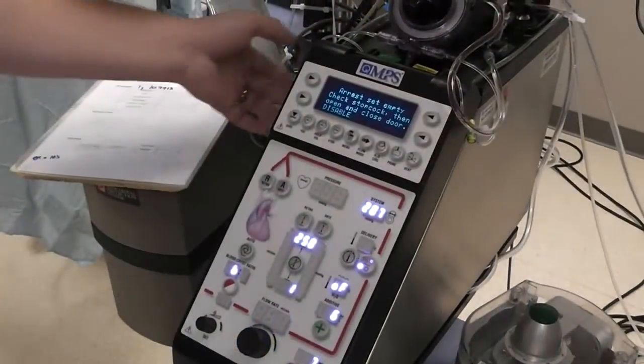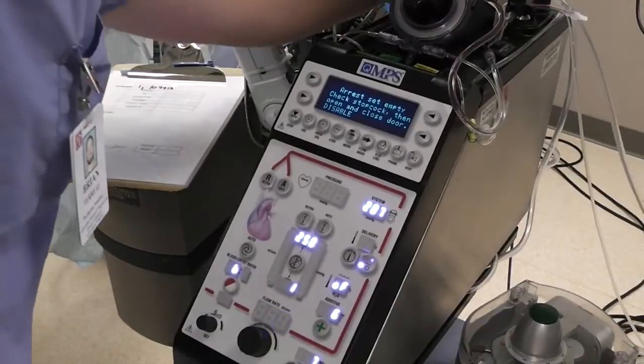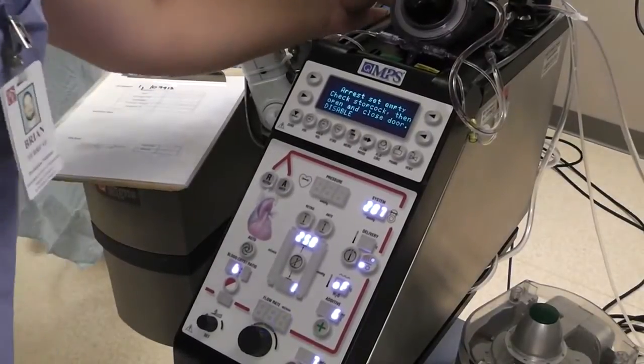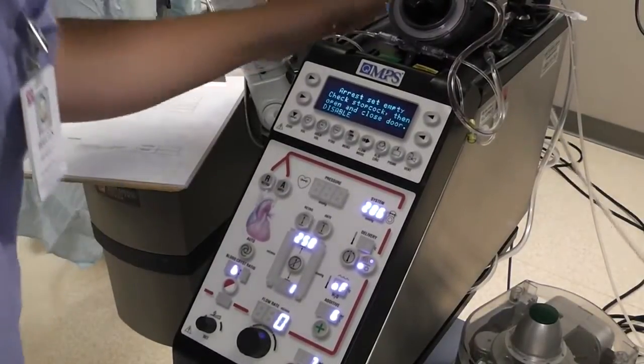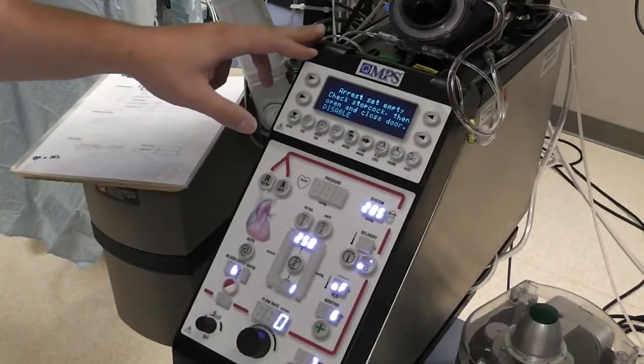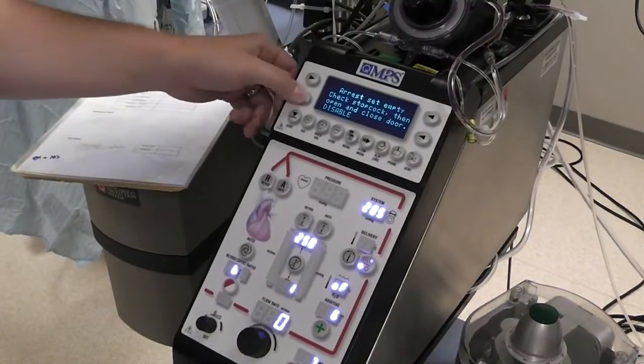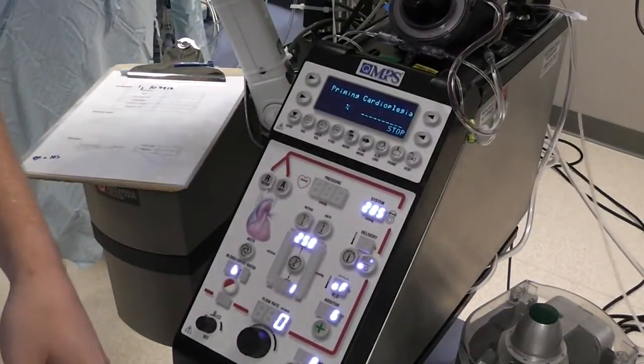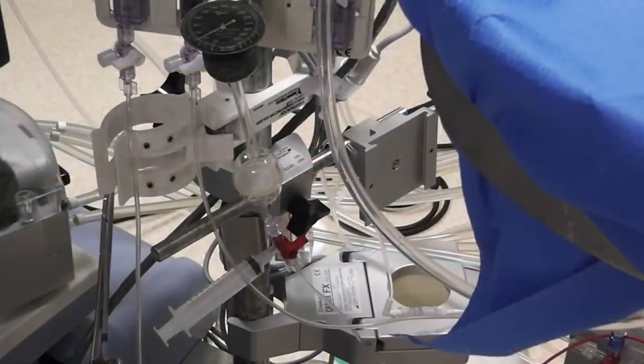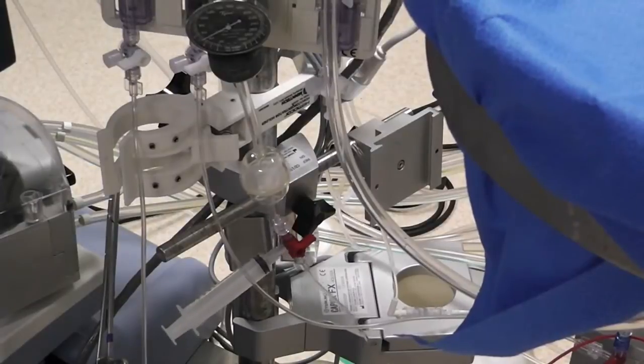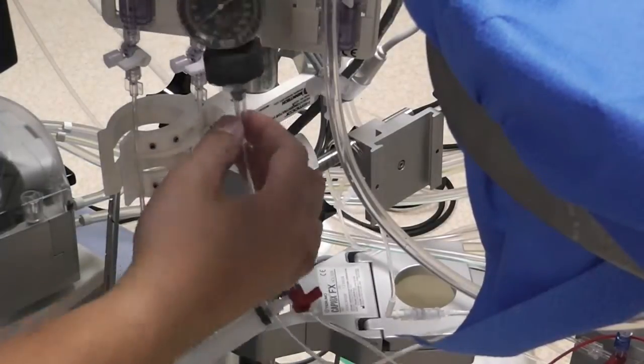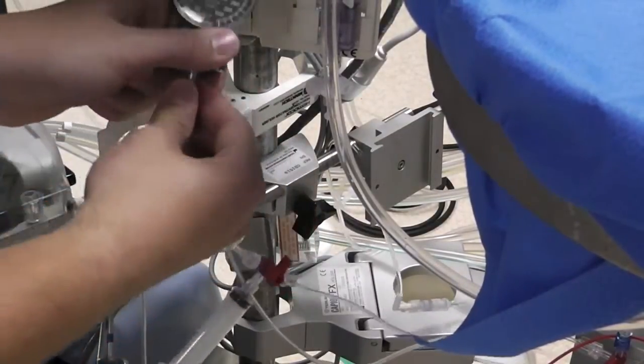Okay, now if you do what I've done here, which is not put the drugs in the Quest before you've primed it, you will get these alarms here that the arrest and then the additive are empty. Just simply hit disable on both of those when they come up. Now I'm going to prime up the pressure monitoring for the arterial line. We're going to remove this from the gauge here.